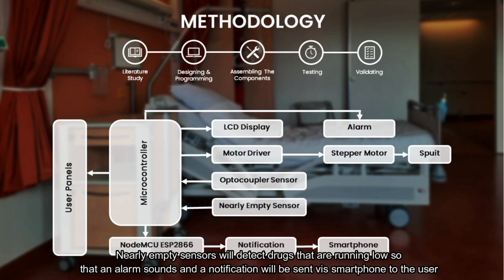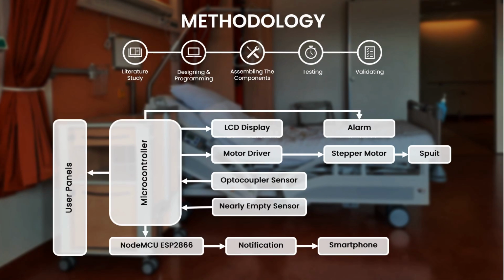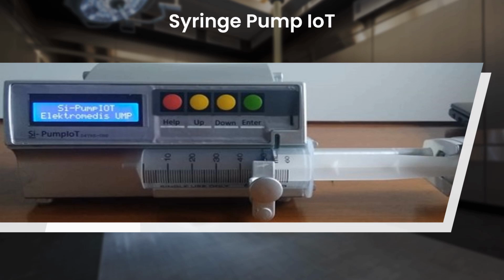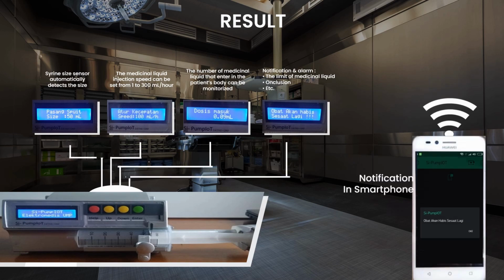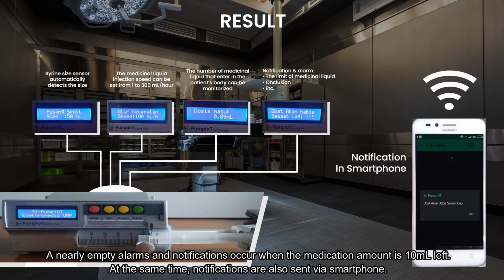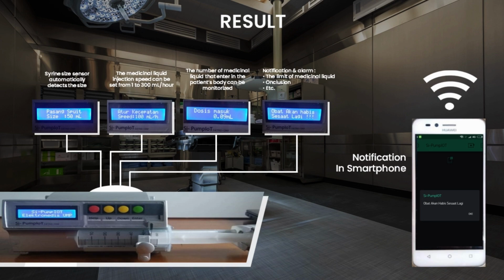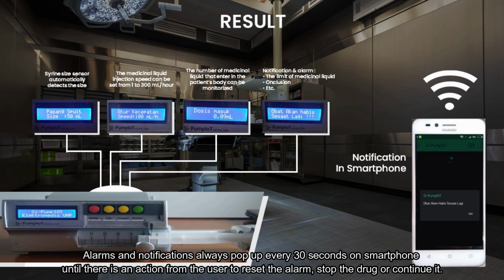Nearly empty sensors will detect drugs that are running low, so that an alarm sounds and a notification is sent via smartphone to the user. Nearly empty alarms and notifications occur when the medication amount is 10 ml left. Notifications are also sent via smartphone. Alarms and notifications pop up every 30 seconds on the smartphone until there is an action from the user to reset the alarm, stop the drug, or continue it.